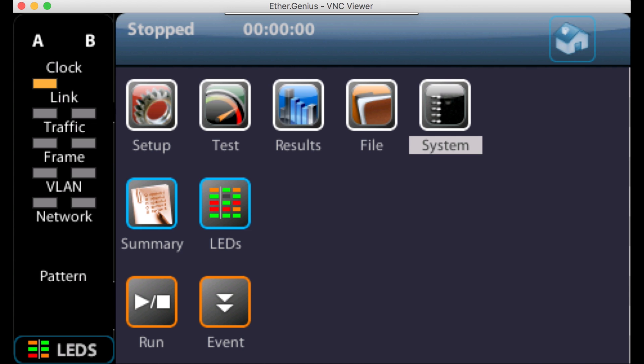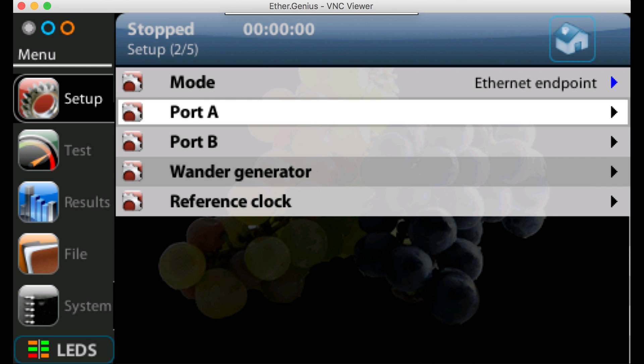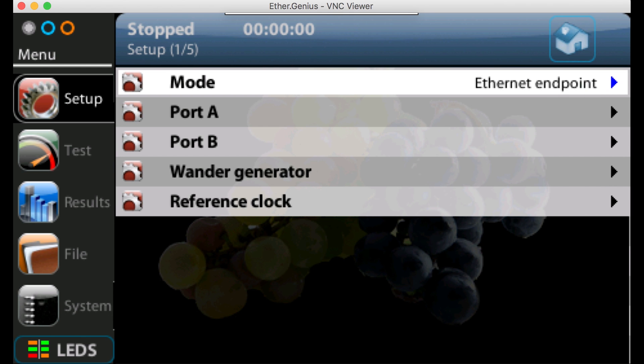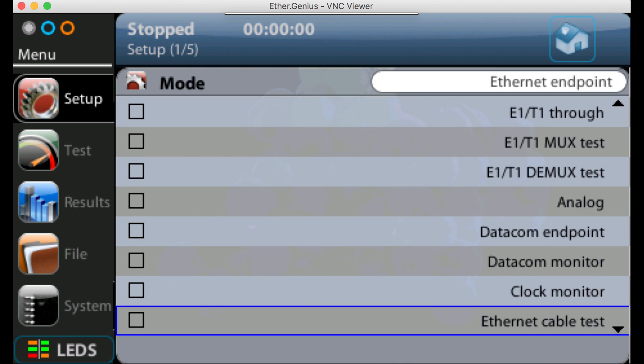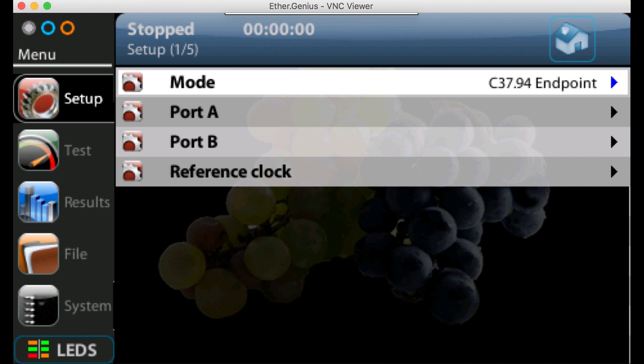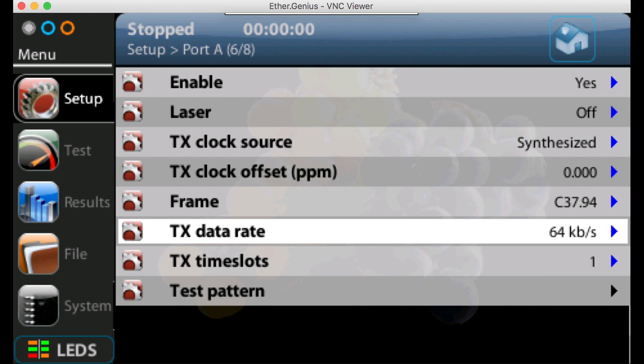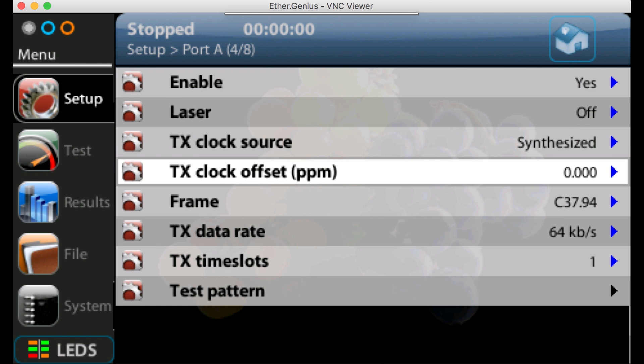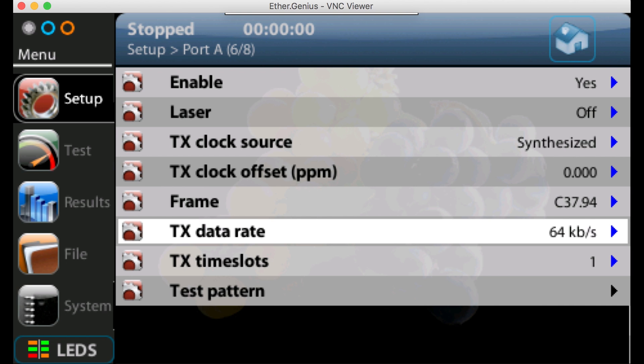We go back to the setup menu. We need to change the mode — at the moment it's set for Ethernet endpoint, but we're going to do a C37.94 endpoint test. So we press enter and use the carousel keys to scroll all the way down and select C37.94 endpoint. Now in C37.94 endpoint mode, we go to port A where our SFP is plugged in, press enter, and we can see that the frame mode is set to C37.94 and the data rate is 64 kilobits per second, or one time slot.